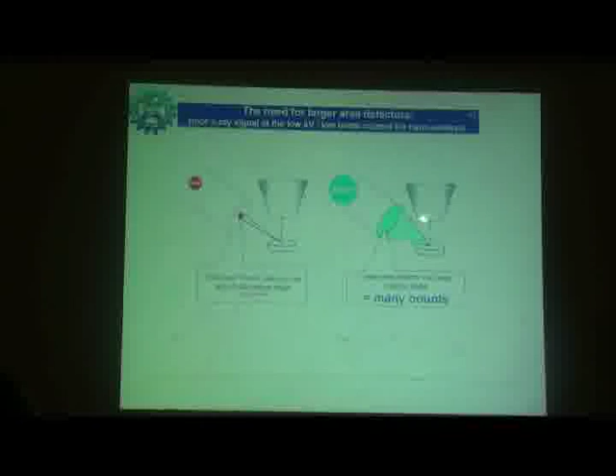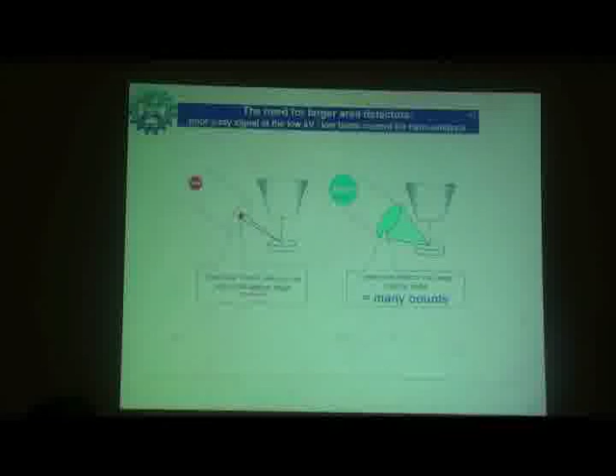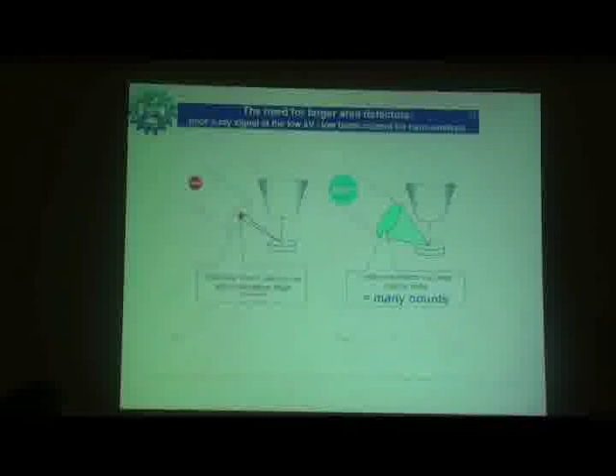So the silicon drift detector is the latest technology which doesn't require any LN2, and you can increase the area by increasing the area of the silicon wafer. So you can have different areas. Normally this is a 10 mm detector and this is an 80 mm detector. So you have more solid angle, so you can get more counts from the same sample area. When you have a high beam current, you can reduce the time of X-ray EDS analysis. EDS analysis requires a lot of time because it requires more counts or more iterations.